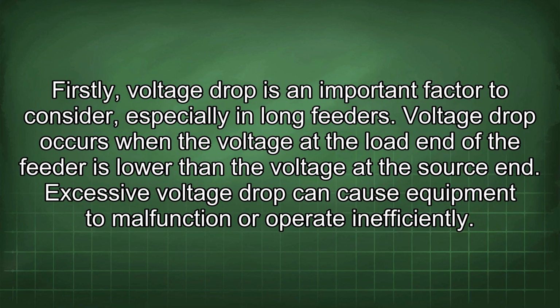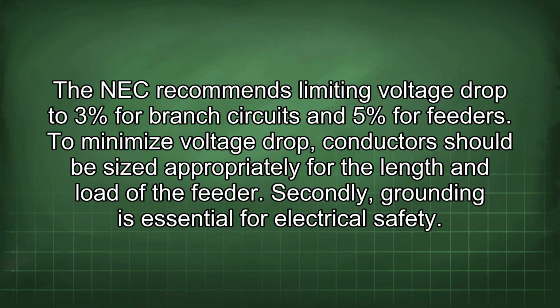Firstly, voltage drop is an important factor to consider, especially in long feeders. Voltage drop occurs when the voltage at the load end of the feeder is lower than the voltage at the source end. Excessive voltage drop can cause equipment to malfunction or operate inefficiently. The NEC recommends limiting voltage drop to 3% for branch circuits and 5% for feeders. To minimize voltage drop, conductors should be sized appropriately for the length and load of the feeder.